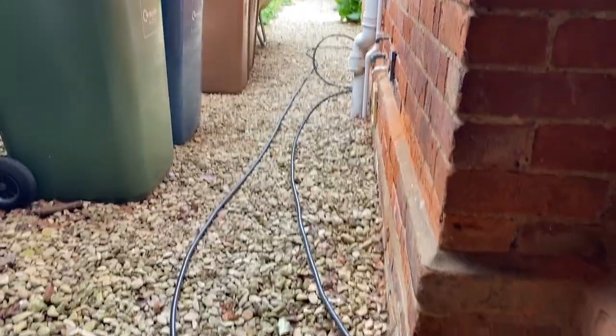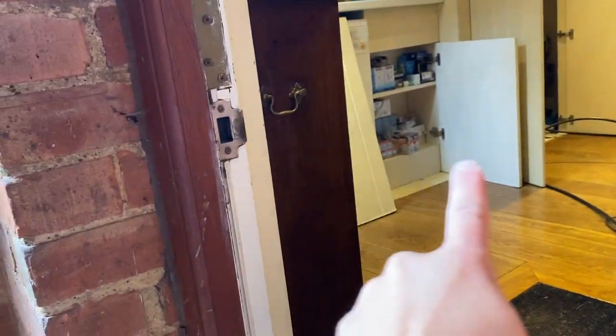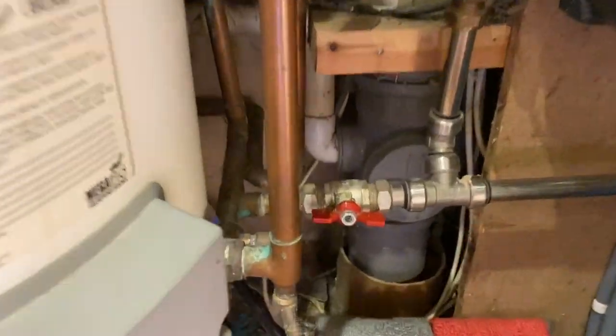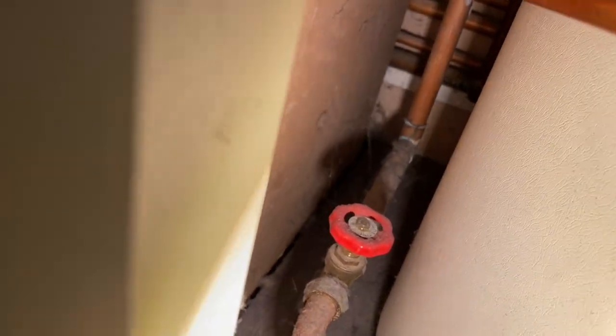So yeah, a little jump in the video. I'm installing an aircon supply at a house today. I'll have a look and show you the route. So it's a 2.5 radial SWA. The aircon guys have got their trunking on, so I've got to get up into that trunking and round on the flat roof, but I've got to get it through this utility. I'm going to come under these units, drill out, pop out and up. Try and get it behind the tank. Somewhere there. And then up.